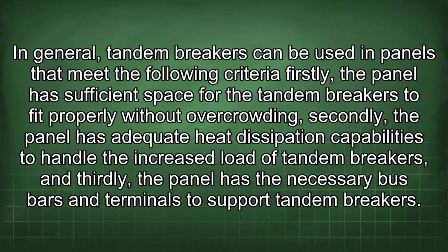In general, tandem breakers can be used in panels that meet the following criteria. Firstly, the panel has sufficient space for the tandem breakers to fit properly without overcrowding. Secondly, the panel has adequate heat dissipation capabilities to handle the increased load of tandem breakers. And thirdly, the panel has the necessary bus bars and terminals to support tandem breakers.